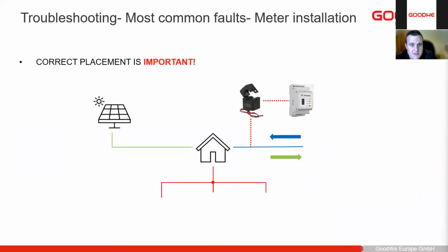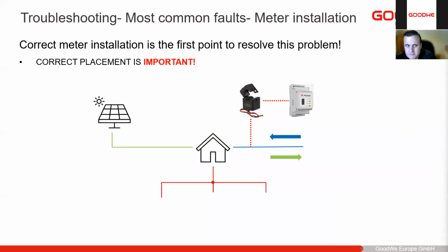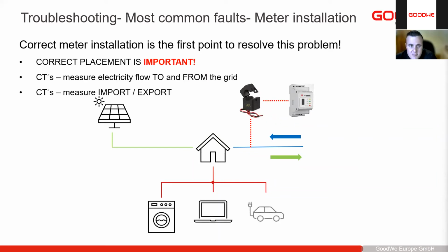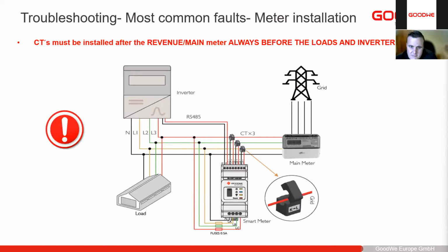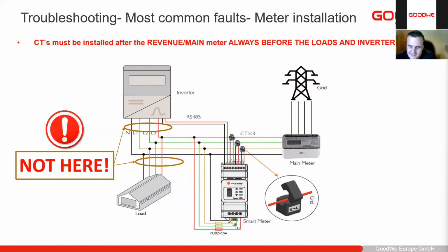So then how do we make sure our smart meter is always installed correctly? The meter placement is very important. The CTs measure the electric flow to and from the utility. So it's very important to place the CTs in this area over here, between the main utility meter and the loads. It shouldn't be between the inverter and the loads. It should be between all the sources. So that's normally installed on your main incomer from the utility. Not there, not there, not there. We need to install it here.